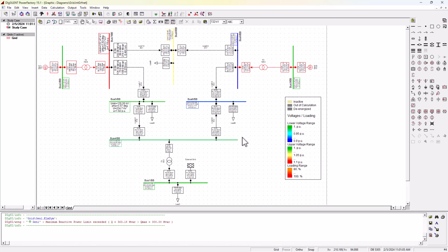It's not very direct, but it does have an effect on the reactive power of the system, because high impedance will cause a voltage drop, and when we have a voltage drop, this will actually cause a change in the reactive power flow in the system, whether it's going to be a negative or positive net reactive power. It will have a cause and effect. And adding that to the load connected to the system, this load is drawing 32 megavolt ampere reactive, and this load is drawing 30 megavolt ampere reactive. So the system here is heavily loaded.